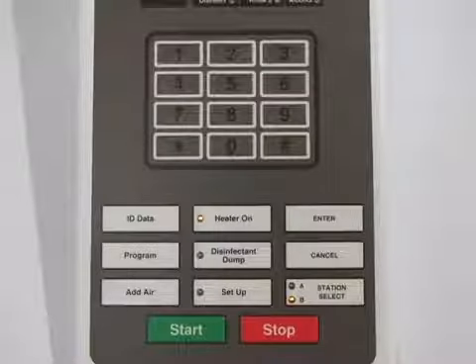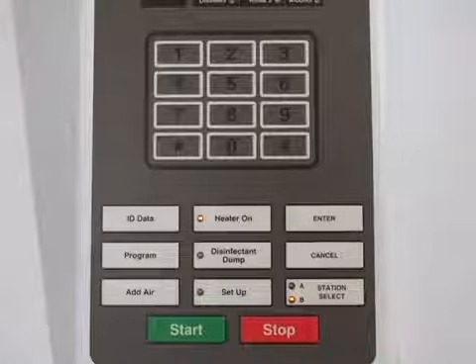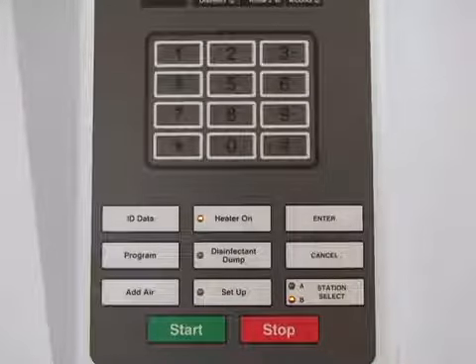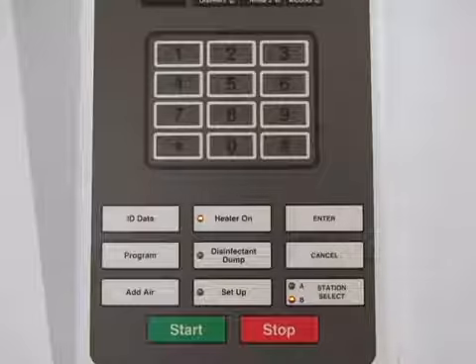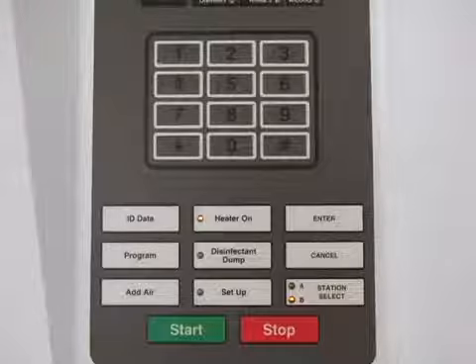When dumping heated disinfectant, do not manually turn off the disinfectant heater. It shuts off automatically when the disinfectant dump cycle is initiated. After fresh disinfectant is fully loaded, the heater will turn back on automatically. When the basin is finished draining, open the lid and remove the floating lid. Wipe the basin, strainer, and drain cover with a damp lint-free cloth. Do not use paper towels. Replace the basin and strainer cover.